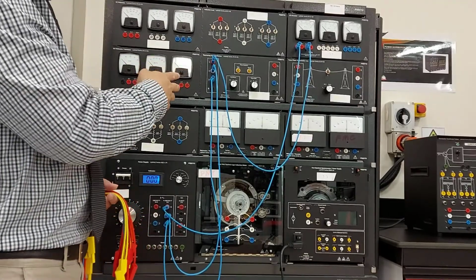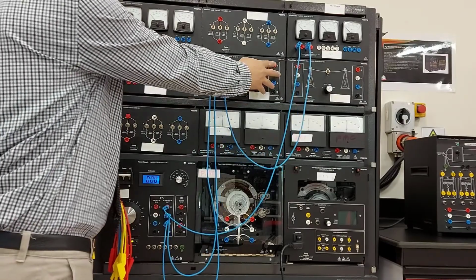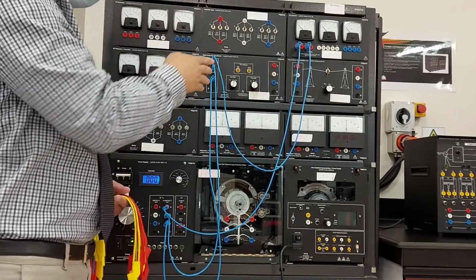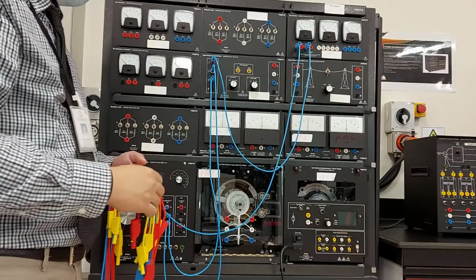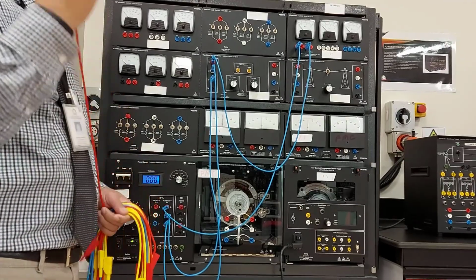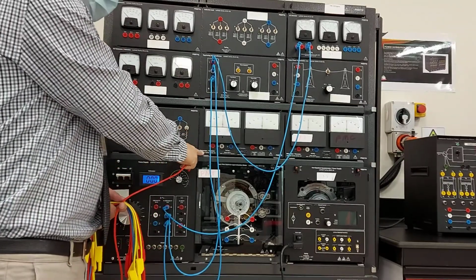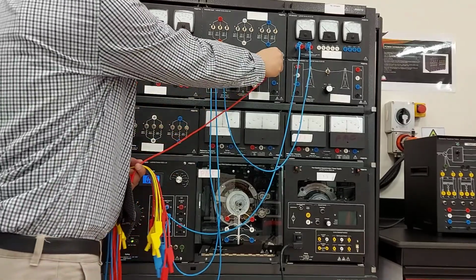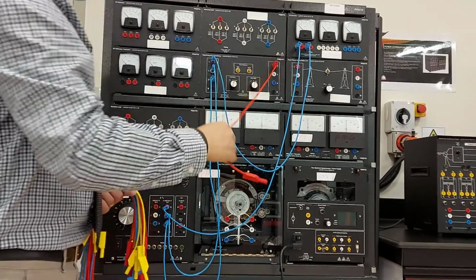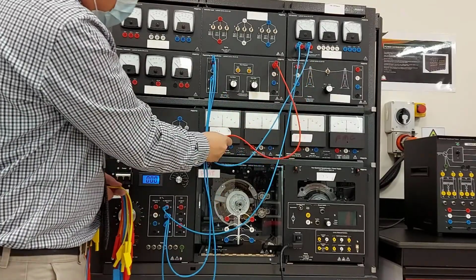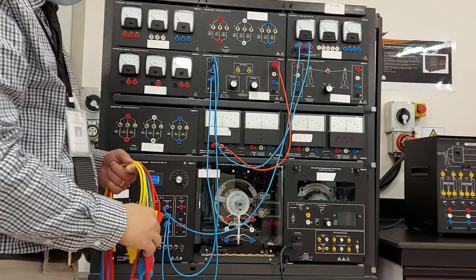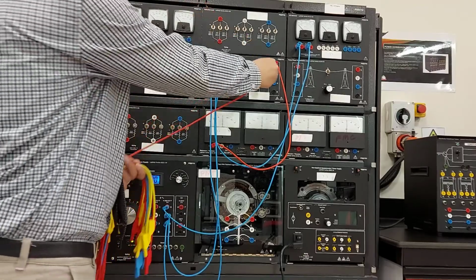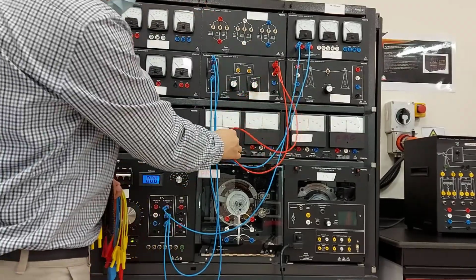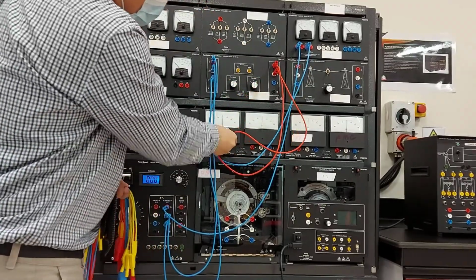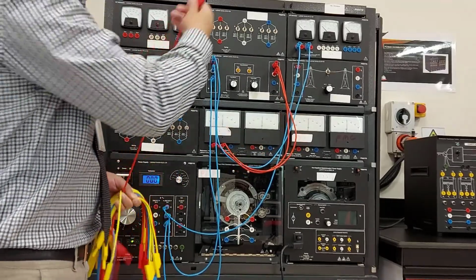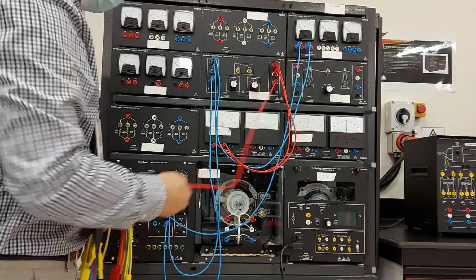Once done, connect the output of the regulating auto transformer to the first 3-phase wattmeter var meter: number 4 to number 1, number 5 to number 2, and number 6 to number 3 of that module.